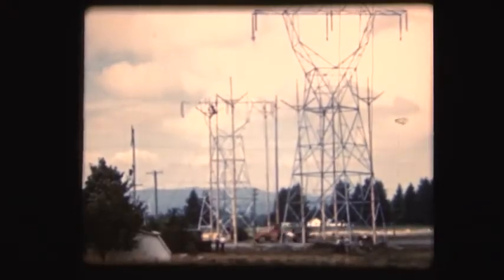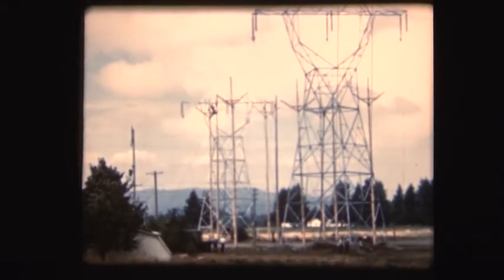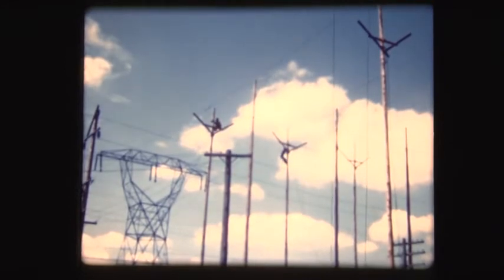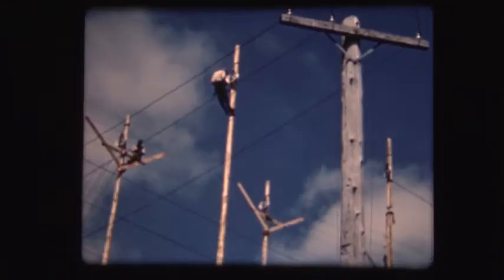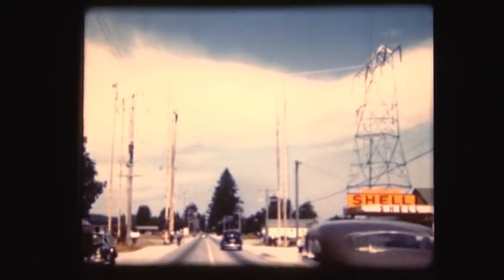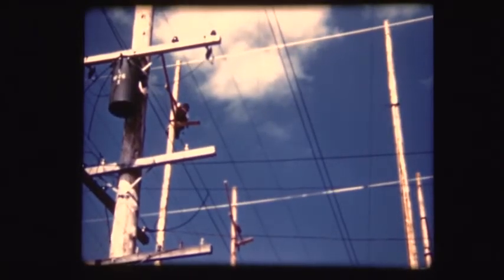When a line must be strung across an obstruction such as a highway, railroad, or other power line, crossing guards are used. These are temporary wood pole structures fitted with sheaves to support the conductor while it is being pulled through. Y arms are usually fitted below the sheaves for added protection. This method makes it possible to cross busy highways without disrupting traffic or even live power lines when necessary.